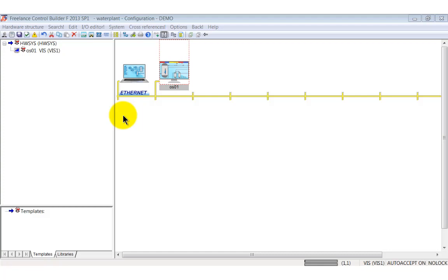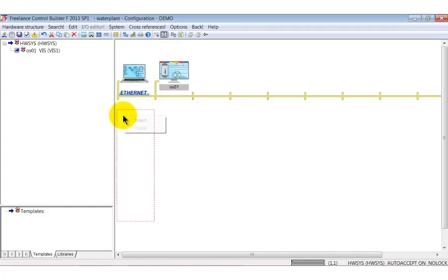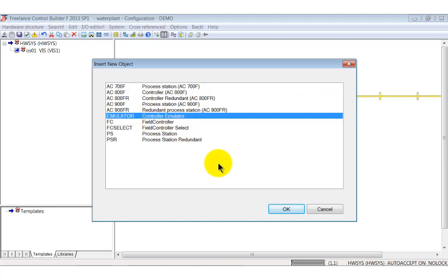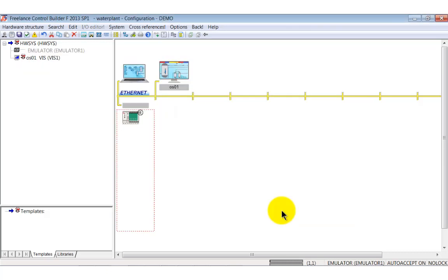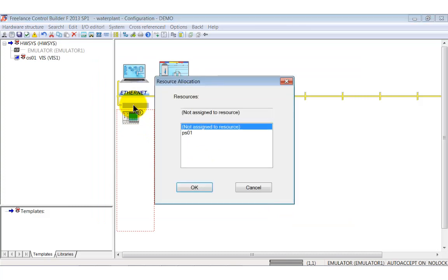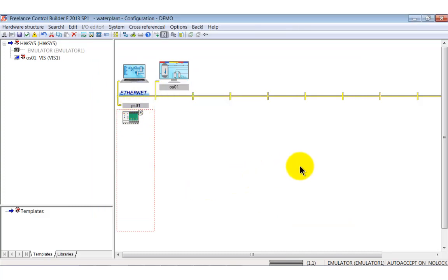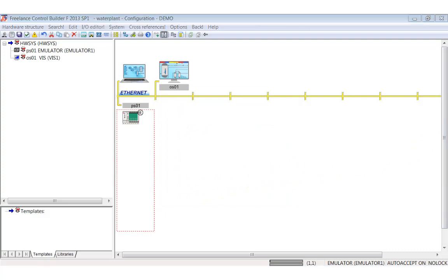Now this hardware element refers to OS1 which we have previously defined in the project tree. Here you see an example how the Control Builder F components work hand in hand. Perform the same steps for the controller emulator. Right click into the field under the ethernet. Select insert controller emulator and allocate it to PS1. This is the place where we define that we use an emulator instead of a real controller AC800F.